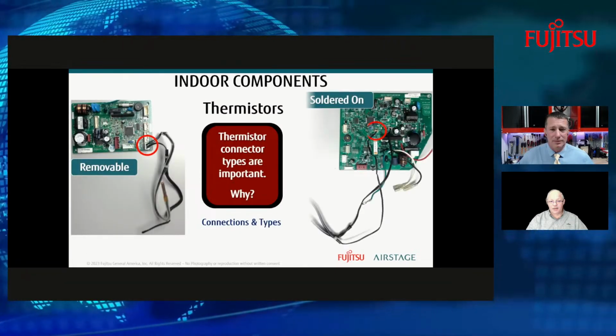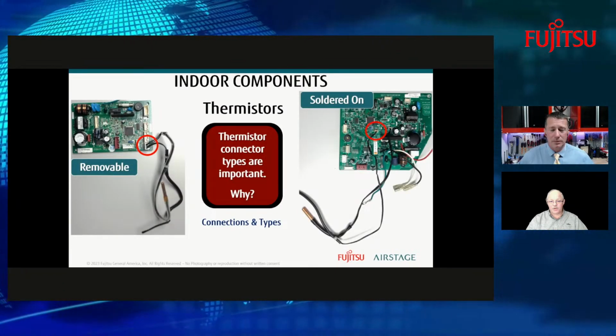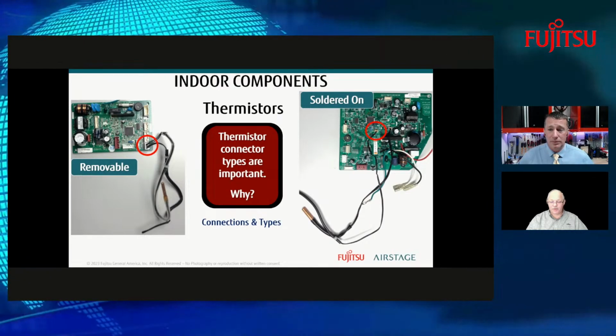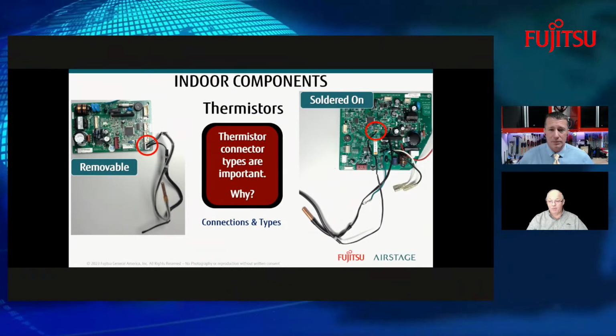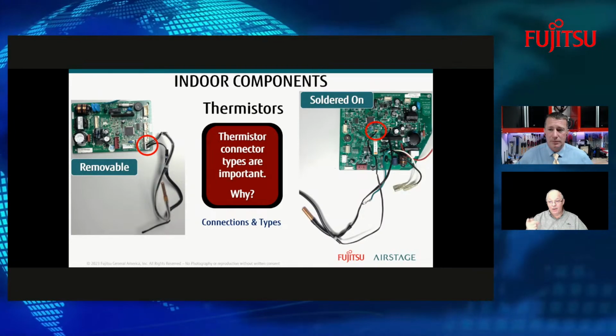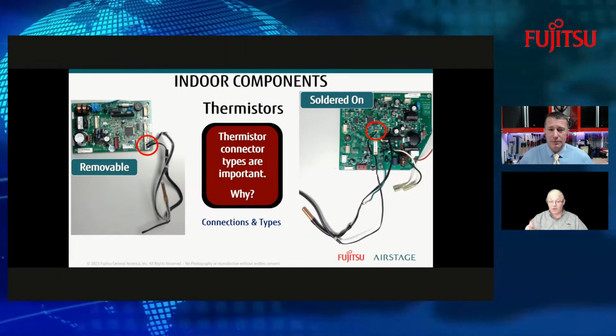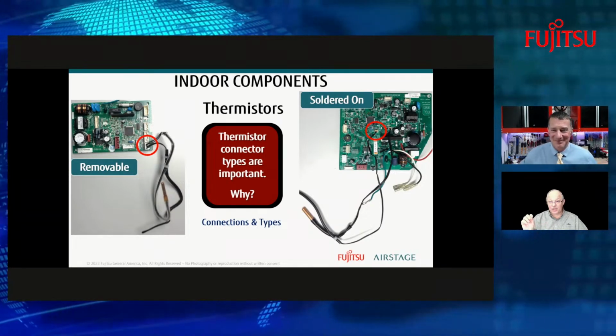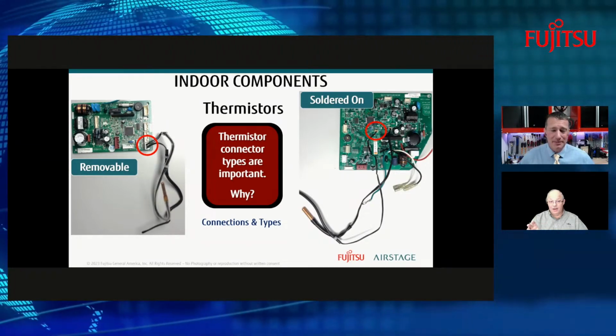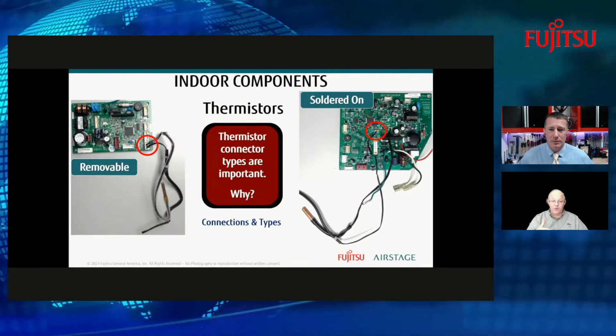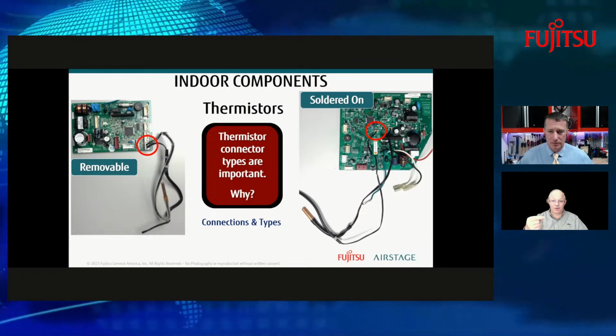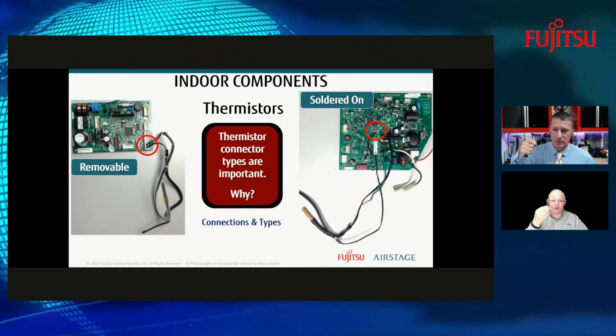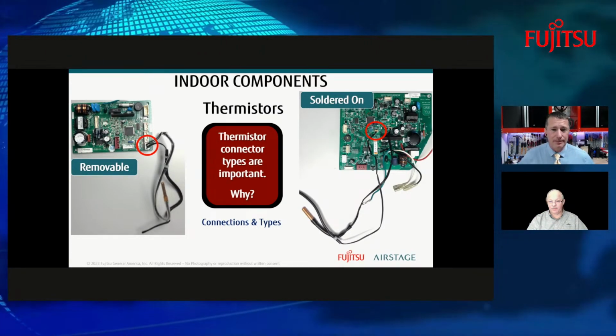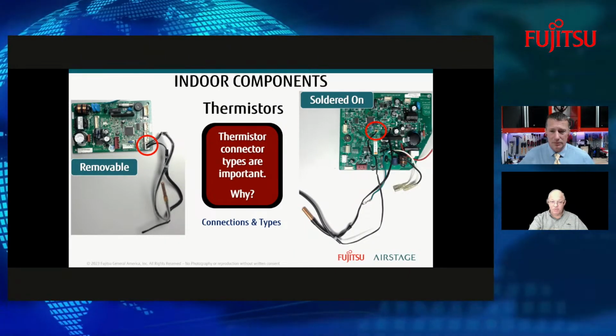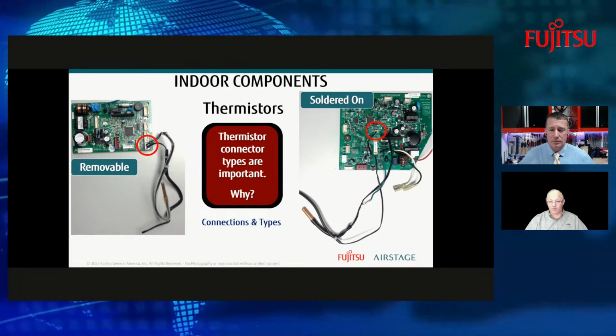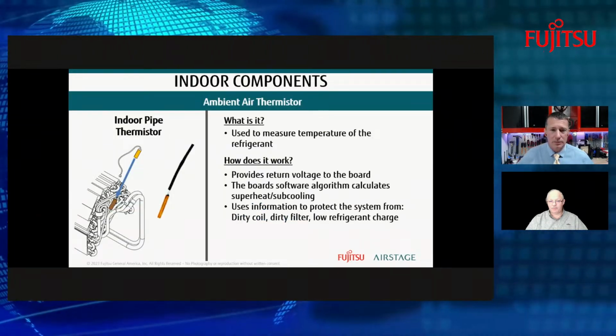All right, let's look at a little bit on the indoor. So these are the indoor thermistors, and I'm sure this varies from manufacturer to manufacturer. But on the right-hand side, you can't pull that off. If you give that a yank, you're going to end up with a whole new board and everything because this one's actually soldered to the board. This thermistor. Oh, okay. The one on the left is removable, and all you do on that is you just push in on the side of the clip. While you're holding it in, you just lift it straight towards you, and it will just come right off. So some are soldered, but the majority are more of a removable style, which I like.